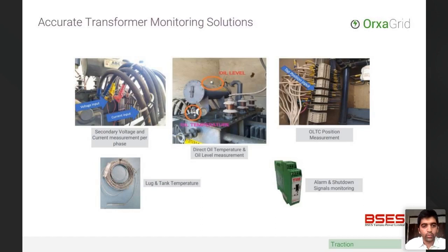In this particular photo, what I wanted to show was that per phase there were two outgoing feeders coming out, and this is quite typical in a lot of transformer installations. So Rogowski coils can also help you combine the loads of multiple lines that are coming out of the same phase as well.